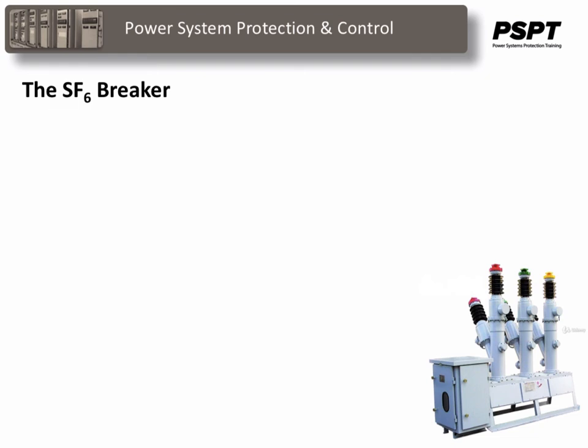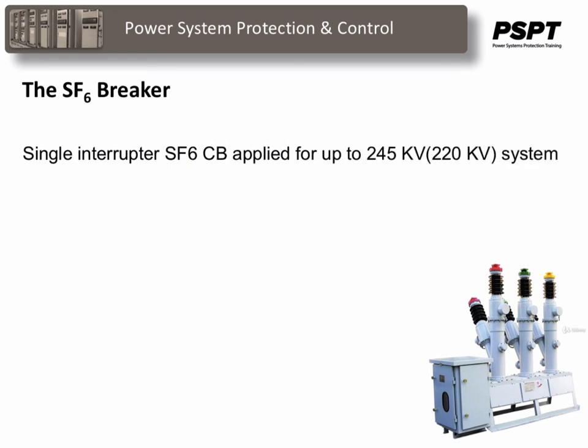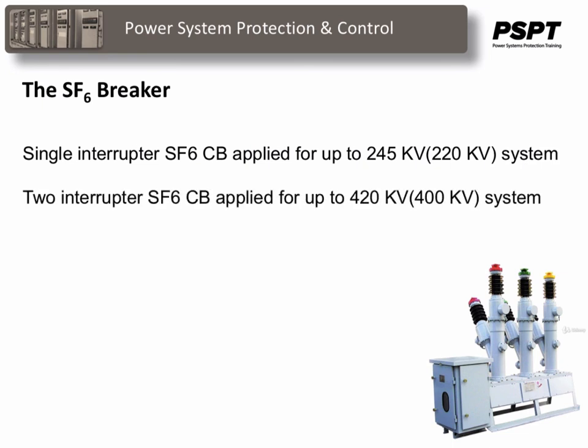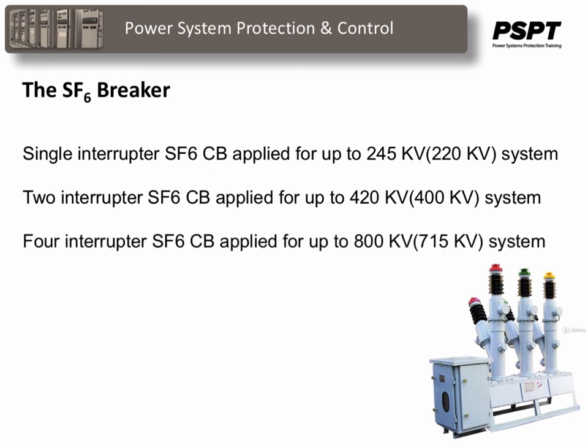There are many different configurations out there of the SF6 circuit breaker, but there are mainly three types, and it all depends on the voltage level of the application. A single interrupter SF6 circuit breaker is used for voltages up to 245 kV. The two interrupter SF6 circuit breaker is applied up to 420 kV, and the four interrupter SF6 circuit breaker is applied up to 800 kV. We're going to look at a single interrupter puffer type in the next couple of slides, and you'll see some of the main features of this type of circuit breaker.